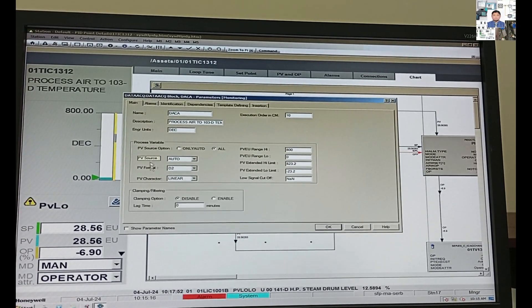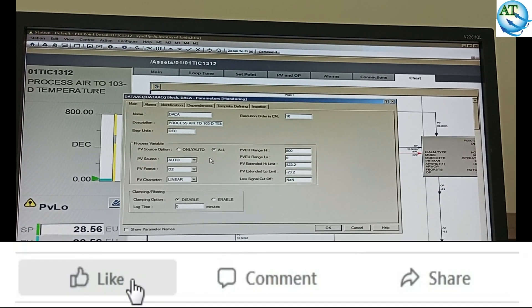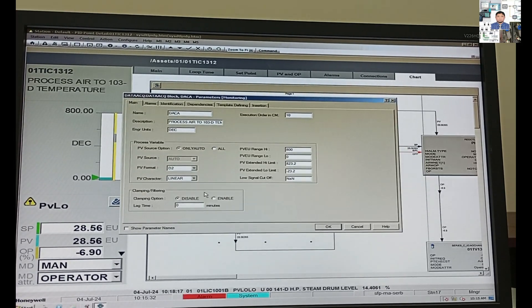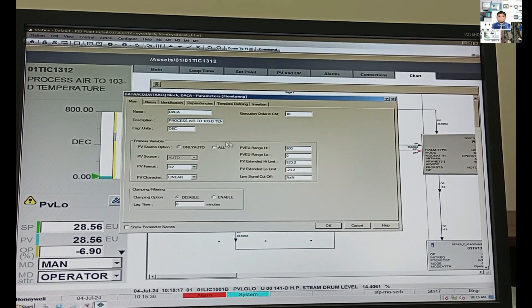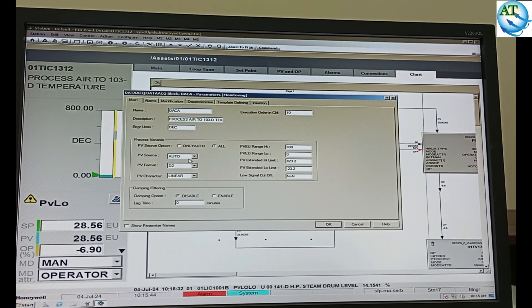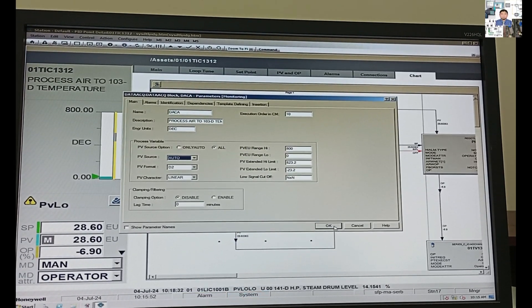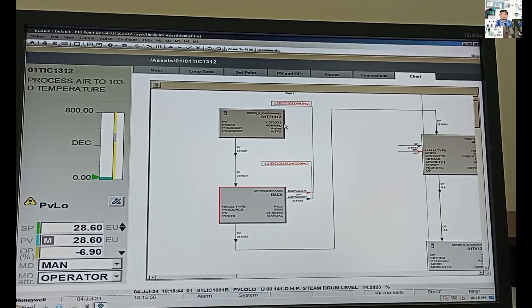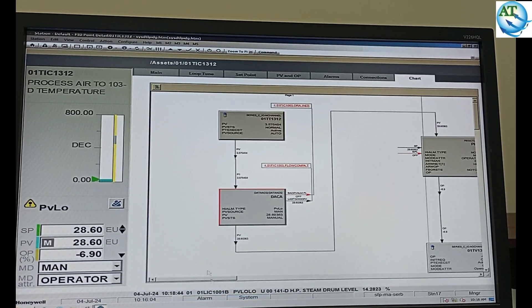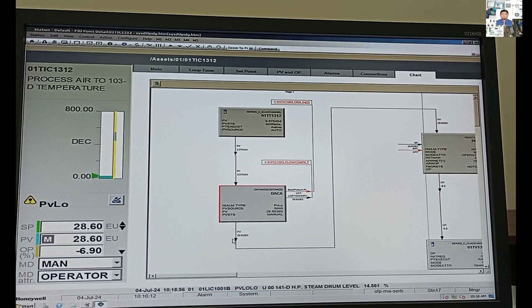We double-click on the data acquisition block. Same way — here is also a PV source option, here is the field source option, and it must be in only-auto mode. Somebody changed it to all mode, so I am changing it back to only-auto mode. All times it should be in only-auto mode. Now we have to change it to all mode, then change the PV source value to man mode. Then the output of this DSA block will be fixed and will not change with the live value of the transmitter. The analog input block is sending value to the DSA block, but the DSA block is in man mode — so the DSA output value does not change.